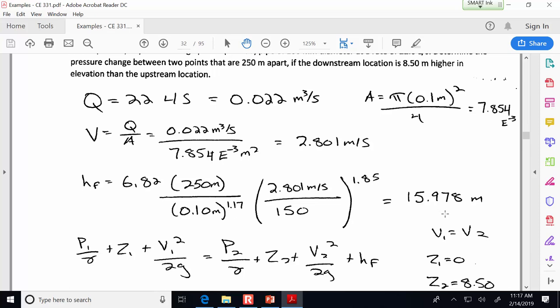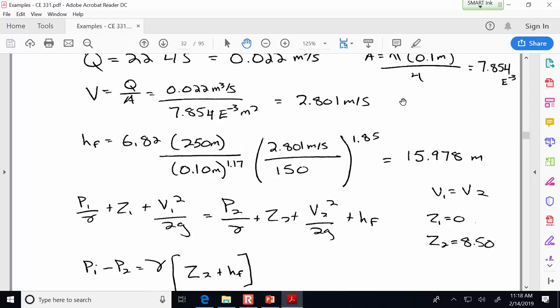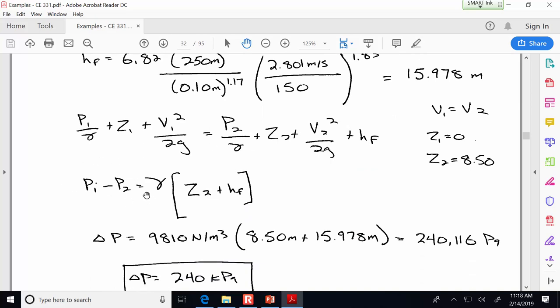The flow rate needs to be in cubic meters per second. The pipe diameter gives us the cross-sectional area, and we get the velocity of the water. Into the Hazen-Williams equation, we find that between these two points 250 meters apart, we lose about 16 meters of head — energy loss due to pipe friction. The pressure change depends on more than just that; the downstream location is also higher in elevation, so that hydrostatic effect also contributes. Rearranging the energy equation, the delta P — defined as P1 minus P2 — is a reduction in pressure of about 240 kilopascals.